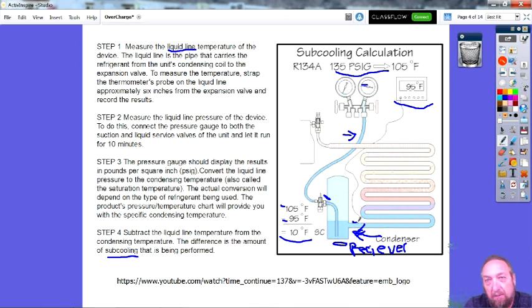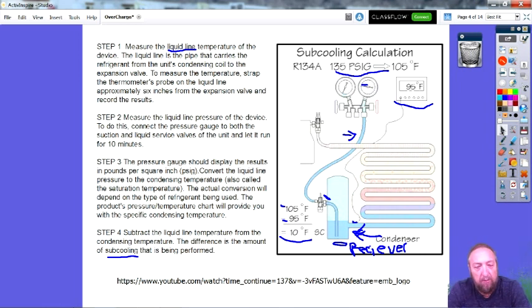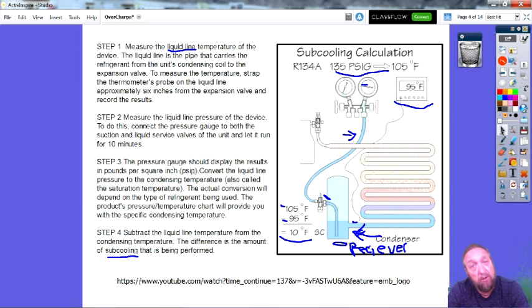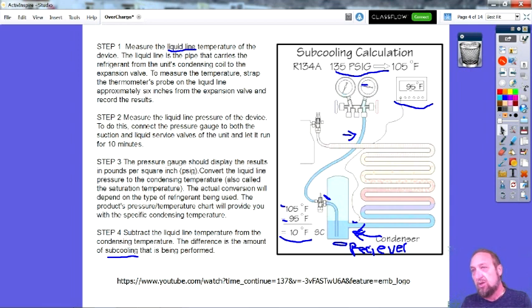Measuring superheat and subcooling will also help you know if the pressures are correct. When talking about restrictions, overcharge, or undercharge — we'll do overcharging today. This is another method to determine if a system is properly charged. In a refrigerator, the manufacturer already determined the math and said it takes 3.5 ounces for a properly charged system. We don't always need to measure superheat or subcooling, but we can.